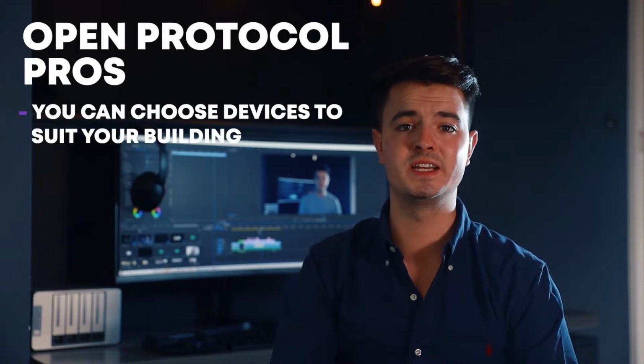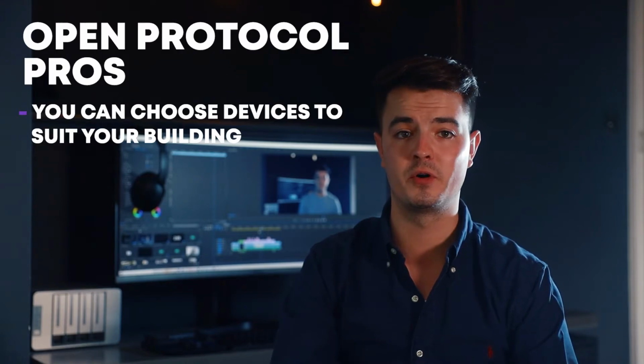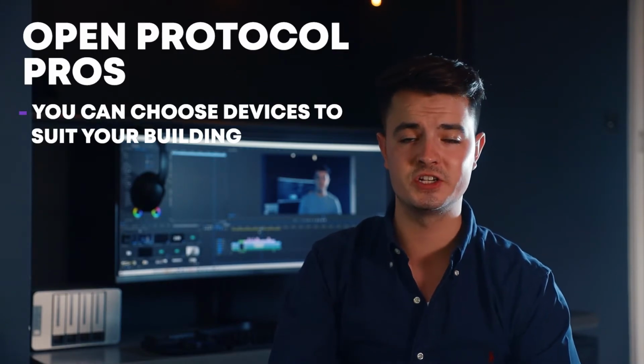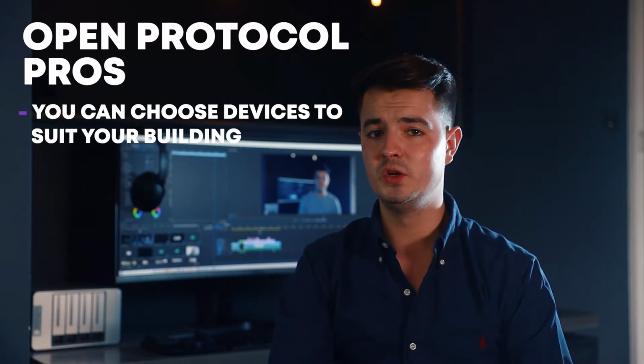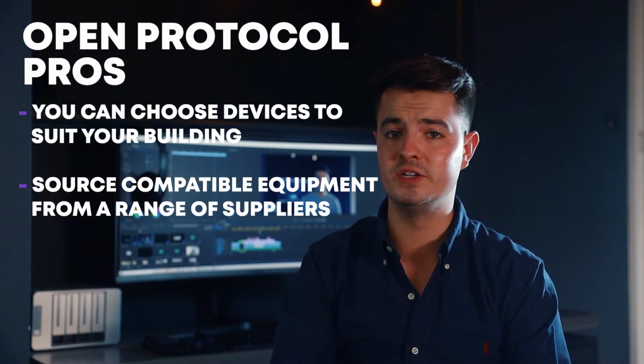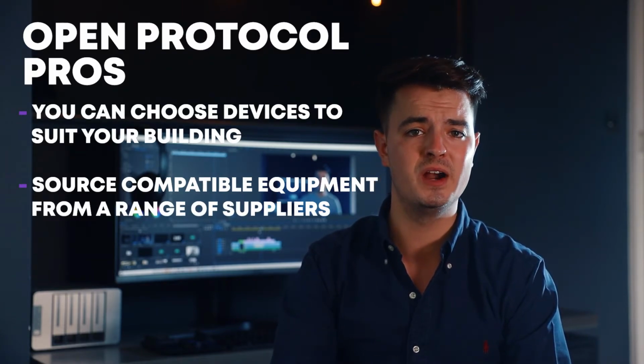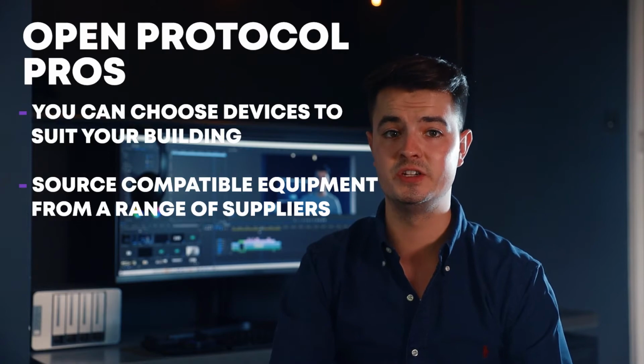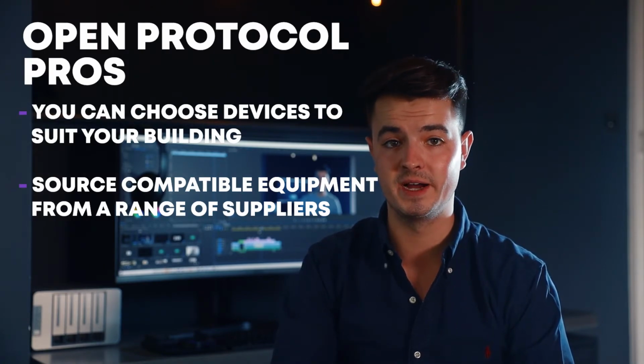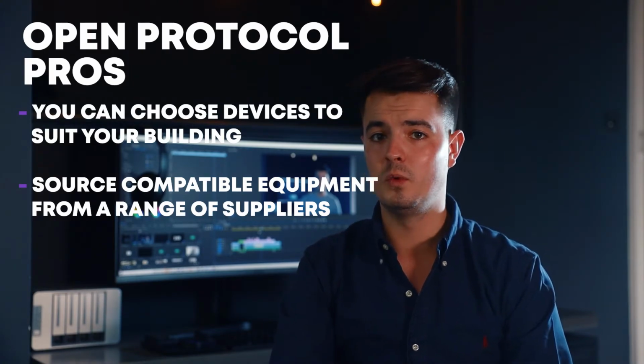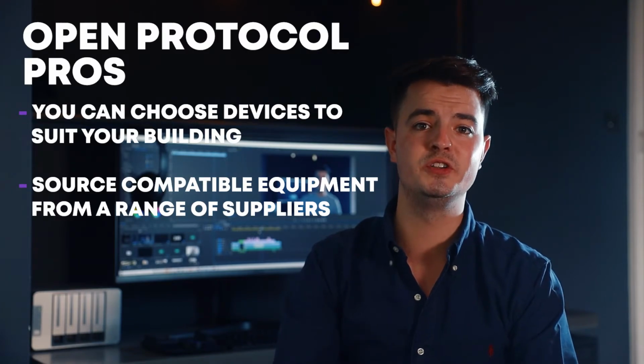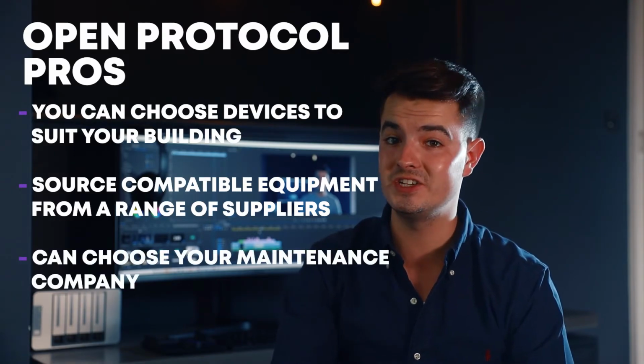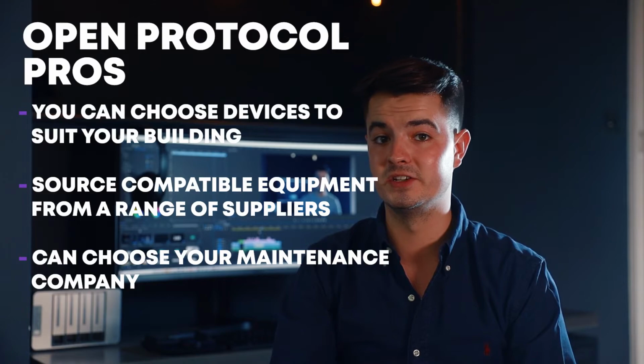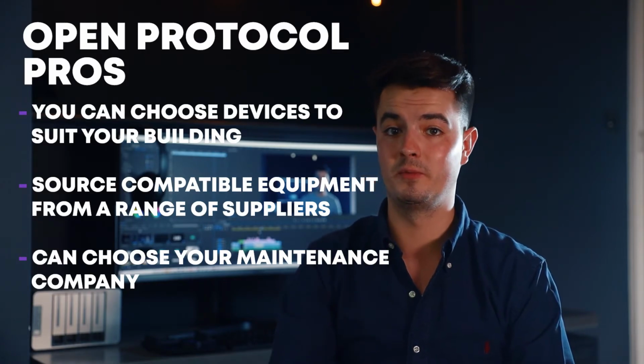We'll start with open protocol. The pros are, firstly, your installer is free to select devices which best meet the requirements of the project design from a greater selection of sources. Secondly, you're free to source your equipment from a wider range of suppliers depending on their individual areas of proficiency, safe in the knowledge that the common protocol means complete compatibility. Finally, once the system has been installed, you're free to choose a maintenance company other than the installation company to carry out the ongoing maintenance regime or to provide additions or upgrades to the system.